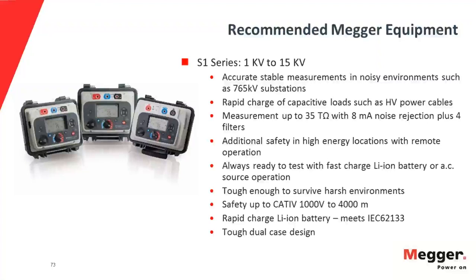The dual case design is a good safety feature. These testers actually have an inner case and an outer case. The inner case is designed against arc flash protection, but when casework is designed for arc flash protection, it tends to make it brittle and prone to crack relatively easily. So consequently, we have a second outer case with a different type of plastic for ruggedized applications, so if it gets banged around, it won't crack. So very good protection of the operator for safety and of the equipment for long life. Okay.